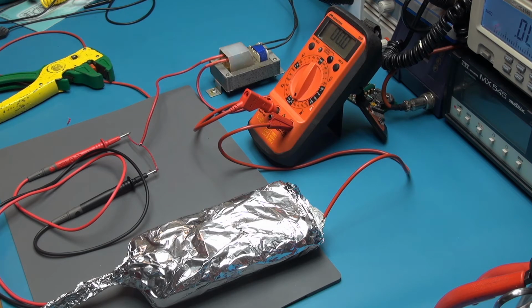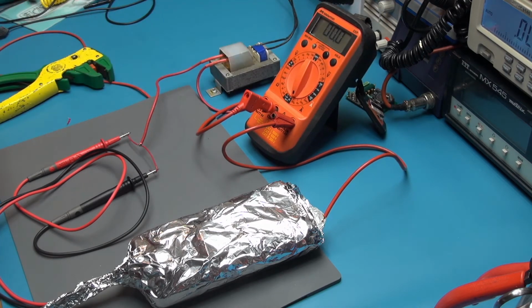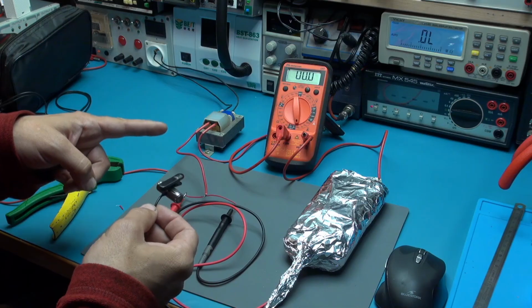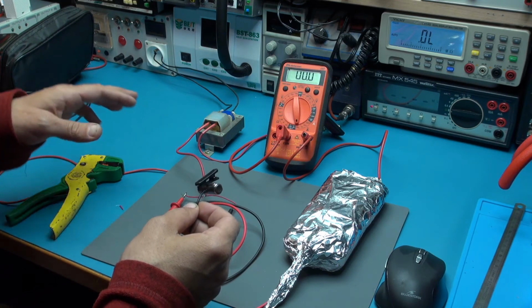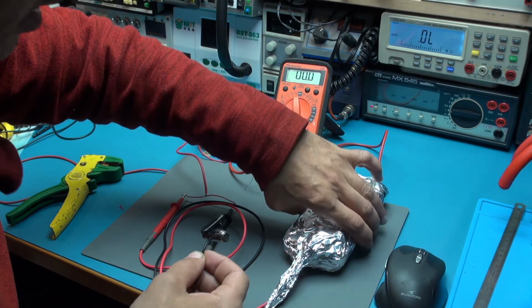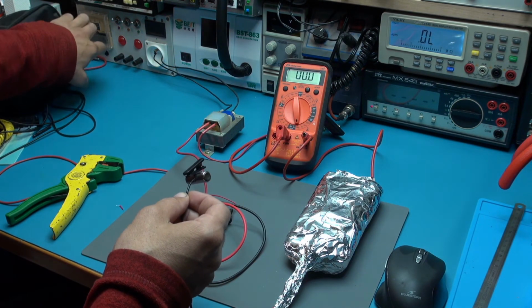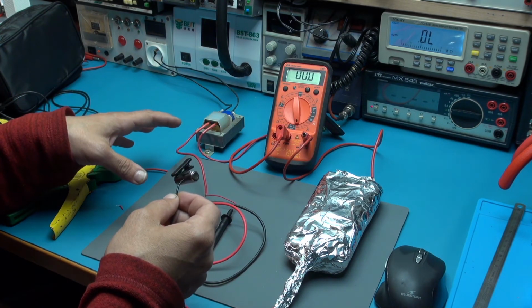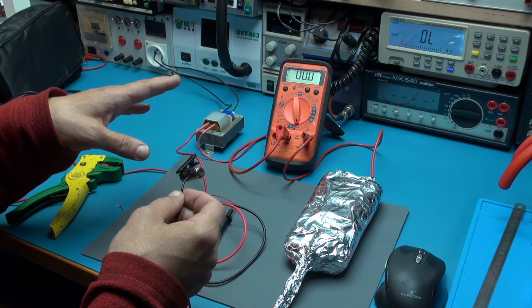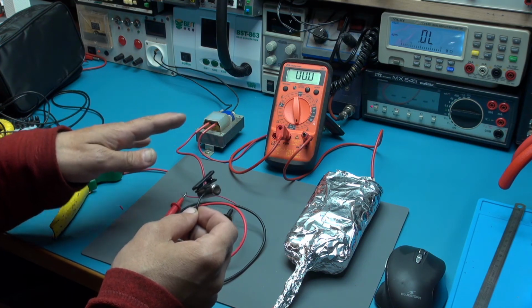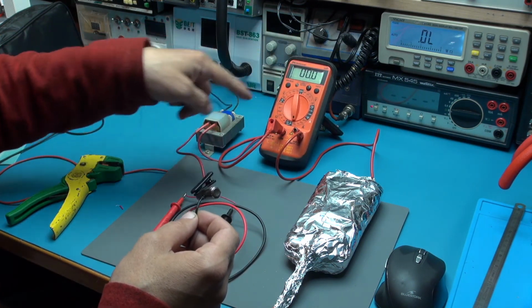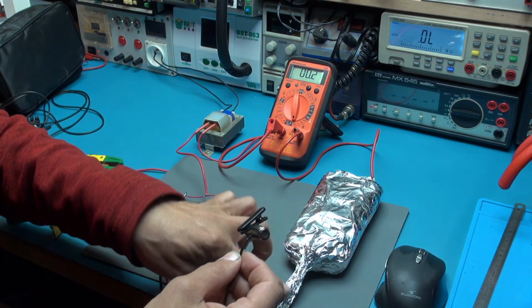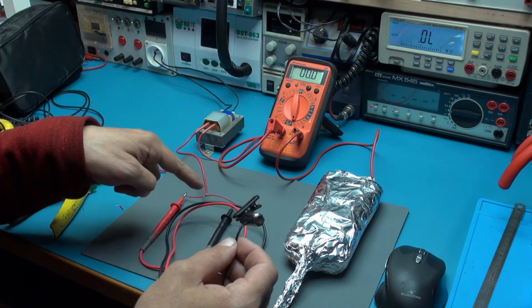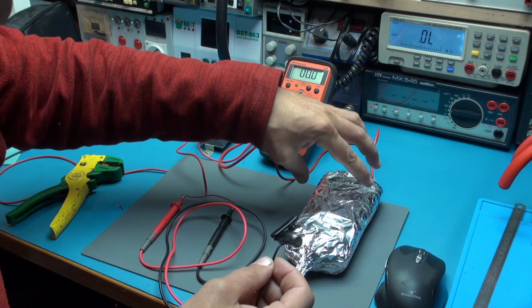So I'm going to pick up the microphone, you can see here, and I'm going to see how this high voltage works with this insulation test. To explain what I'm doing here, the high voltage is coming from this transformer. You must understand that this voltage is very high, on the order of 4,000 volts alternating, and this multimeter is able to see the current going through the surrounding plastic and the wires, the copper inside the apparatus, going through the plastic.